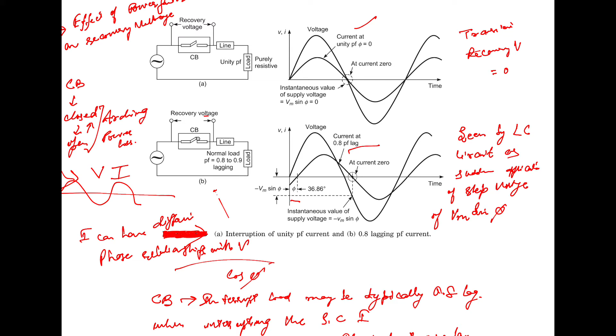Now let us consider the third case. In the third case, you will see that the no load magnetizing current of the transformer is shown. The transformer is open circuited, and the no load magnetizing current is quite small in magnitude as compared to the voltage, as compared to the full load current. So magnitude wise, it is not a problem to interrupt such a current. However, the magnetizing current has a highly lagging power factor angle. You will see that in this case the current is lagging the voltage.